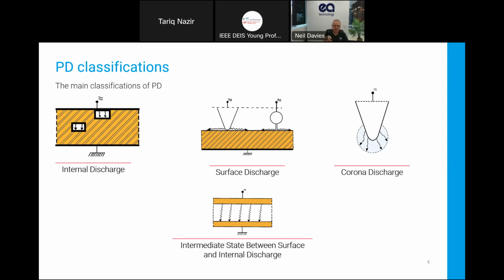And the last type of discharge that we come across relatively frequently is sort of an intermediate state between the internal and the surface discharge. So it's like a gap discharge, floating metalwork. It can be called contact discharge. And this is where you get quite high levels of pulses, usually high amplitude and high numbers of pulses of activity that spark across a defined gap. So you end up with another distinct type of characteristic, some of it with the internal discharge characteristics of quite high amplitudes often, and some of the surface discharge characteristics of a quite high repetition rate.